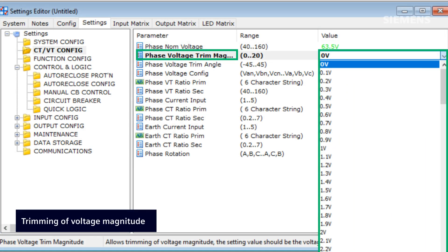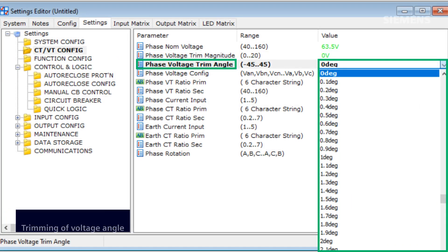The phase voltage trim magnitude allows for the adjustment of voltage magnitude; the setting value is the voltage that needs to be added to correct the phase nominal voltage. The phase voltage trim angle setting allows trimming of voltage angle; the value entered should be the angle required to correct the measured voltage angle.